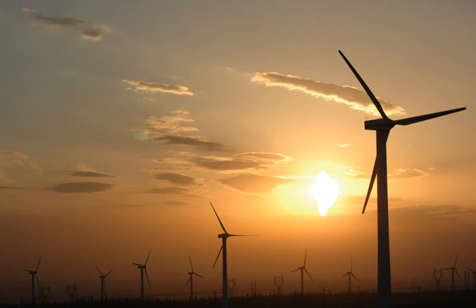Almost all large wind turbines have the same design: a horizontal axis wind turbine having an upwind rotor with three blades, attached to a nacelle on top of a tall tubular tower. In a wind farm, individual turbines are interconnected with a medium voltage, often 34.5 kV, power collection system and communications network. In general, a distance of 7d, 7 times the rotor diameter of the wind turbine, is set between each turbine in a fully developed wind farm. At a substation, this medium voltage electric current is increased in voltage with a transformer for connection to the high voltage electric power transmission system.